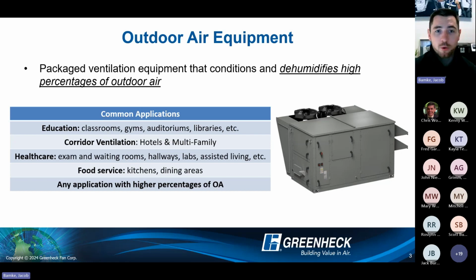So outdoor air equipment, what do we mean when we talk about outdoor air equipment, specifically on the DOAS side? We're talking about packaged ventilation equipment that conditions, and the big keyword is dehumidifies, high percentages of outdoor air. We break those up into two different things. One is that dehumidification process. We design our equipment to dehumidify down to about 50 to 55 degrees. Can go below that, don't have to dehumidify, but that's how our equipment is sized.